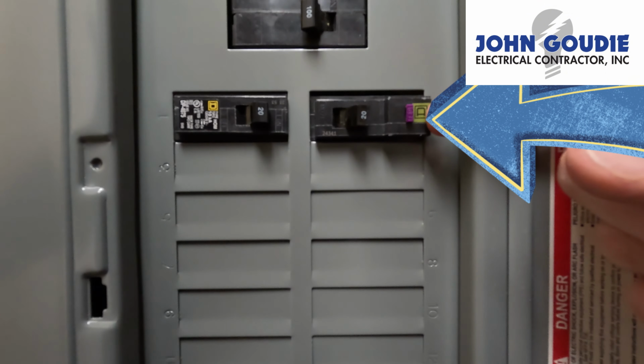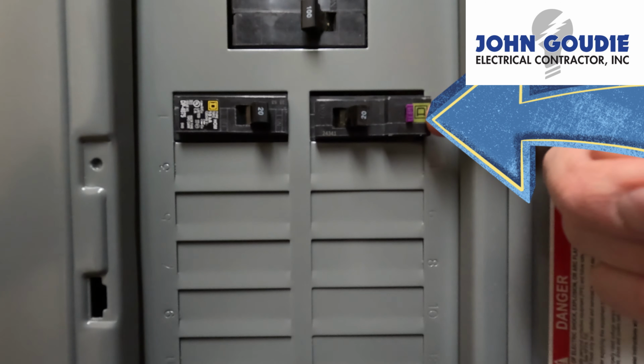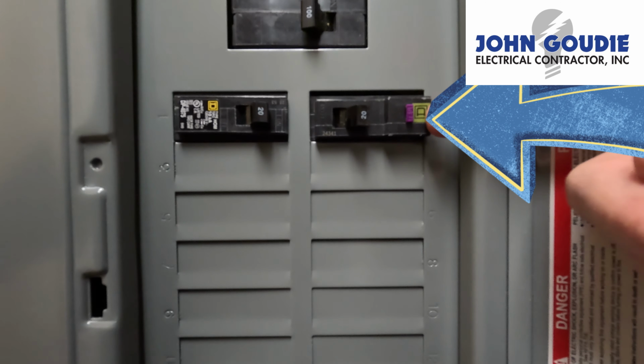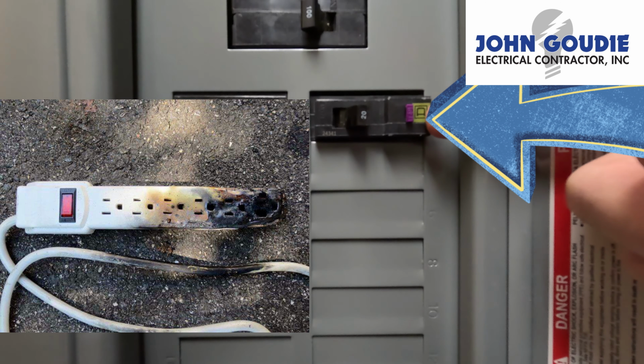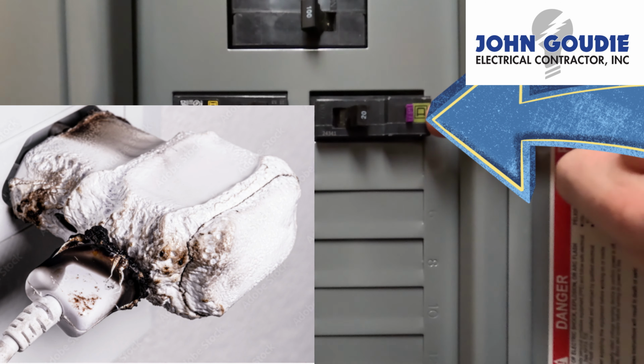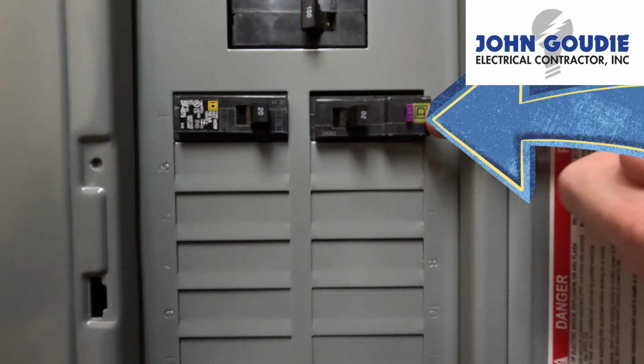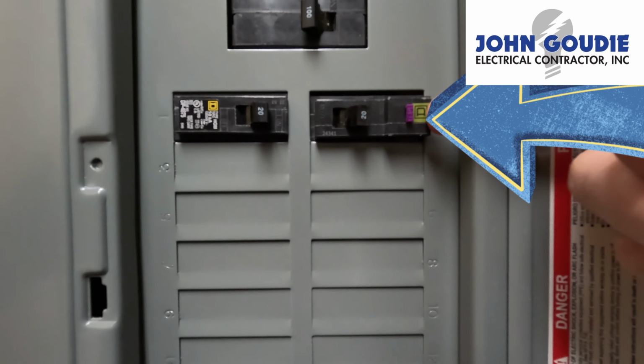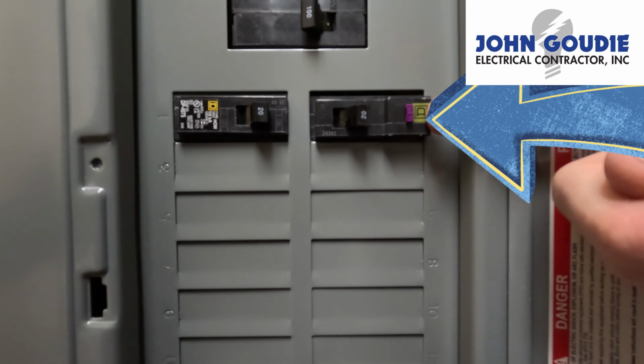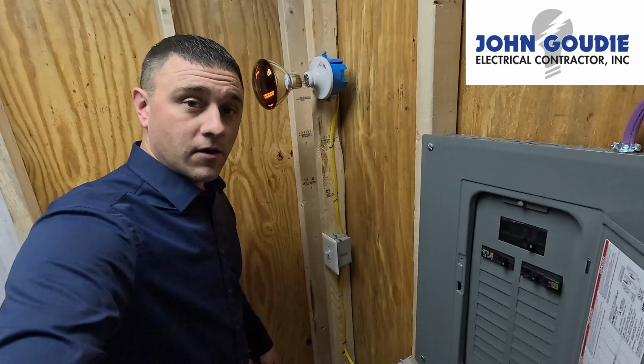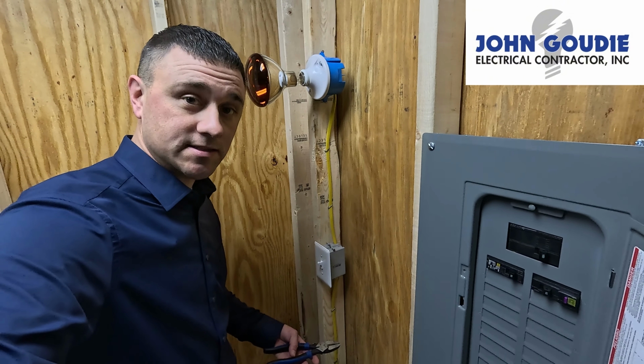Examples of things that you would have plugged in that could have a loose connection within it and could start to arc would be things such as power strips, cell phone chargers, space heaters, really anything you have plugged into that circuit where arcing is happening. This breaker is going to sense it and it's going to trip. So it's a much, much safer option. They are more expensive than a regular circuit breaker, but they do a very good job preventing electrical fires in houses.